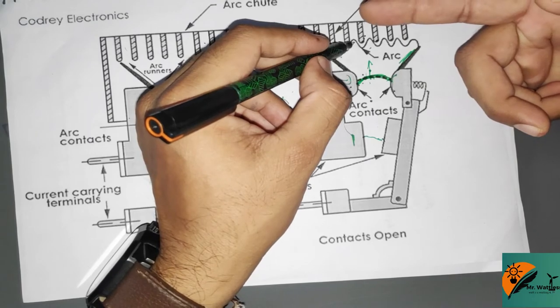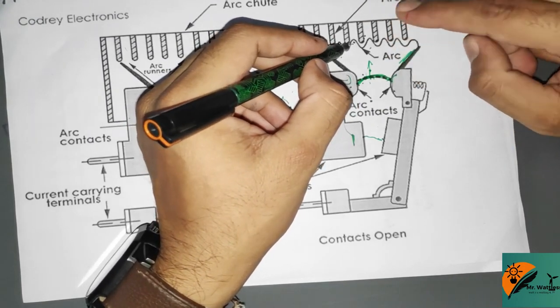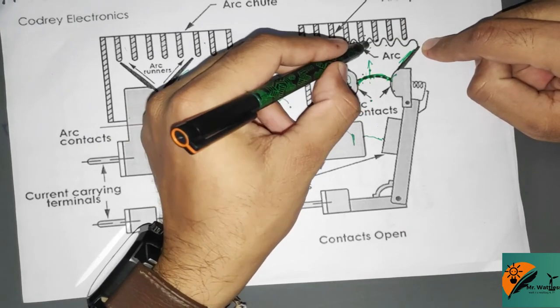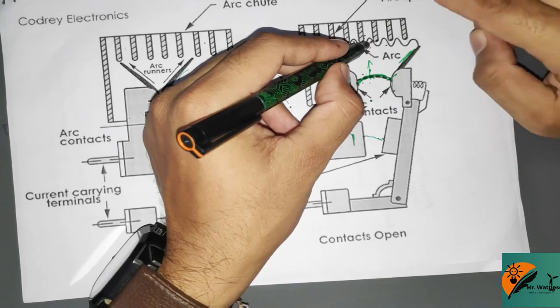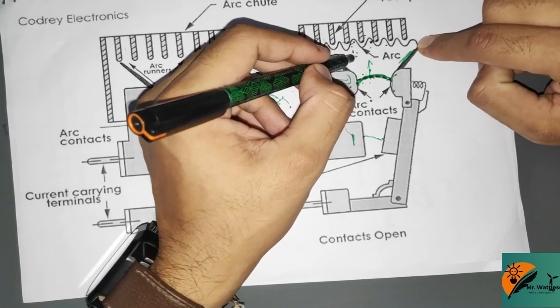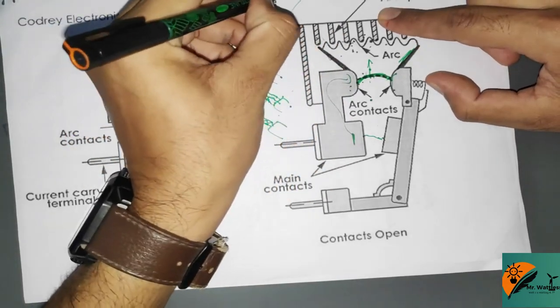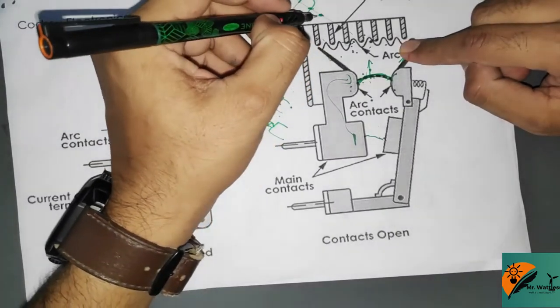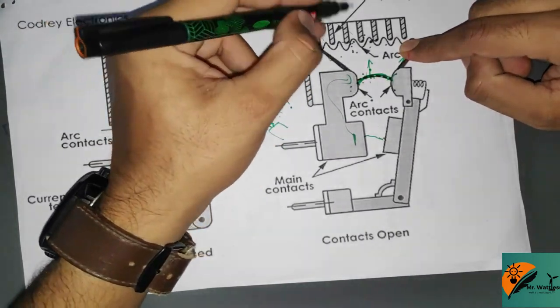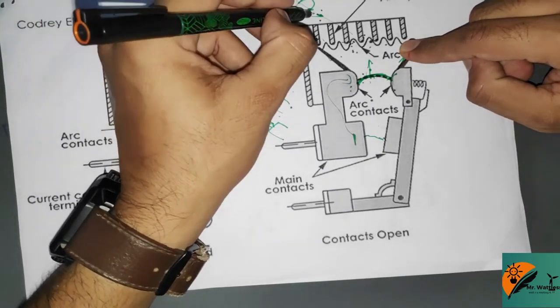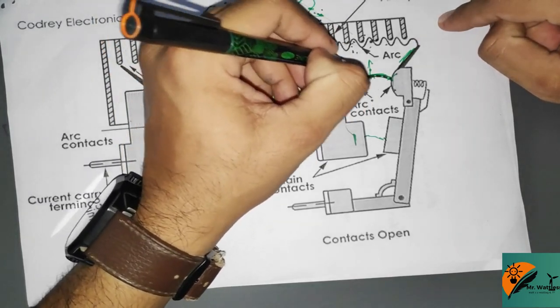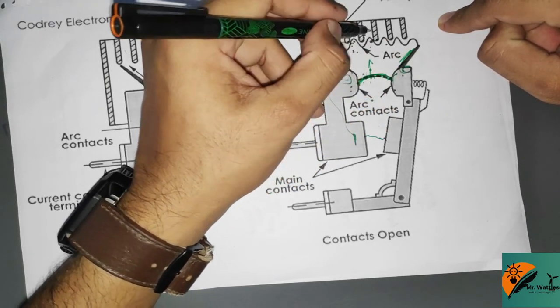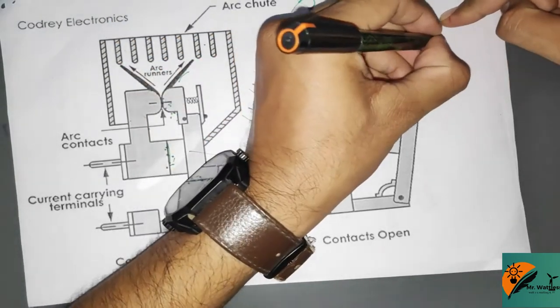The arc gets extinguished as the resistance of the arc is increased. Due to lengthening and cooling, the arc resistance increases, which reduces the fault current and will not allow it to reach a high value. The current zero points in the AC wave will cause arc extinction. With increase in arc resistance, the voltage drop across it goes on increasing. Whenever the arc leaves the contacts, it is passed through arc runners. With the help of blowout coils, which provide a magnetic field, the arc experiences a force given by electromagnetic theory: F = BIL.